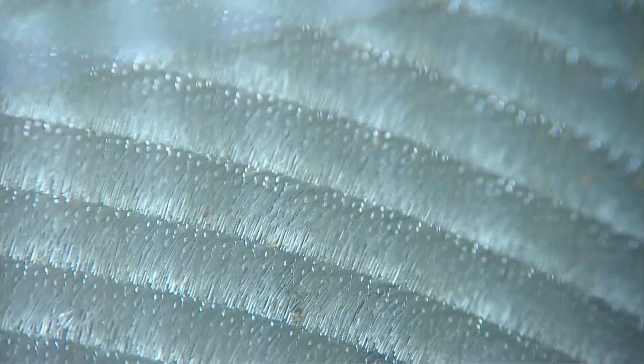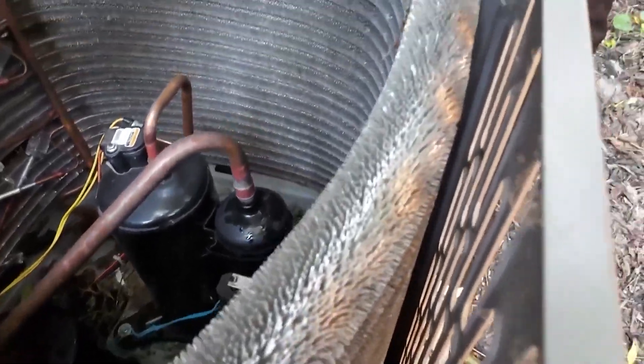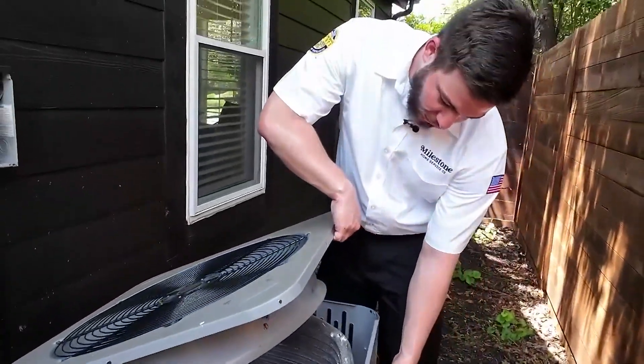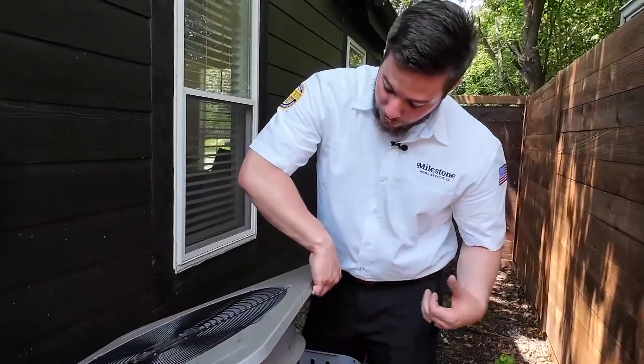Then there's the condenser. If the unit is too dirty to see through, the condenser is likely working too hard and not properly. And if you can't get air sufficiently across these coils here, what will happen is the equipment on the inside can overheat.